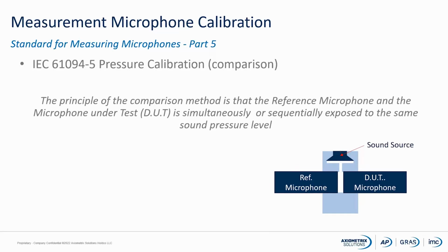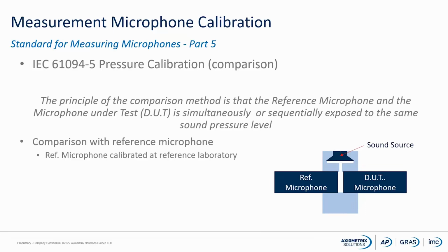So the principle with the comparison method is that you have the reference microphone, you have the microphone under test, and they are tested either simultaneously or sequentially, and they must, of course, be exposed to exactly the same sound pressure level. So we can compare with a reference microphone, or we can also do a comparison via a pistonphone or a calibrator.